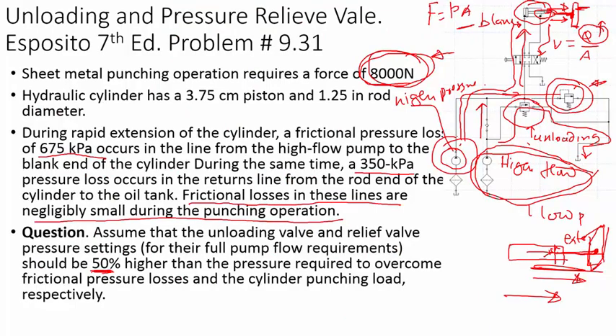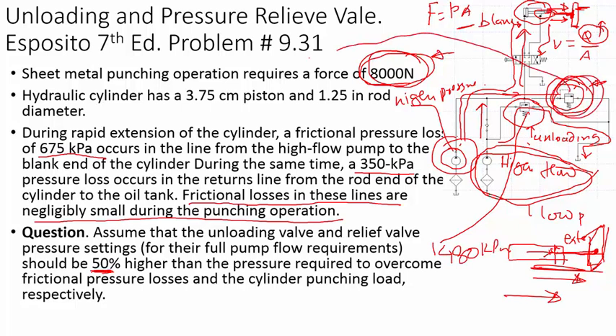To summarize: the unloading valve should be set at 1480 kilopascals, and the pressure relief valve should be set at 10865 kilopascals.